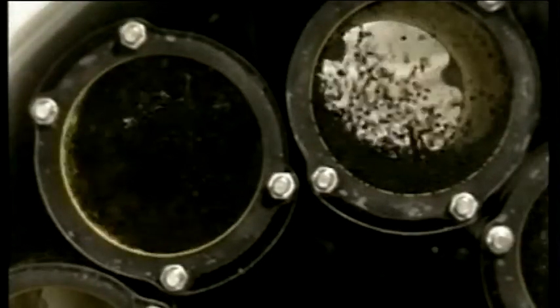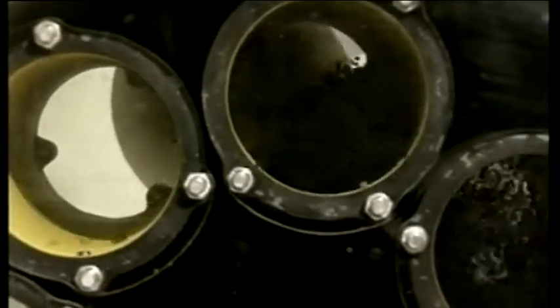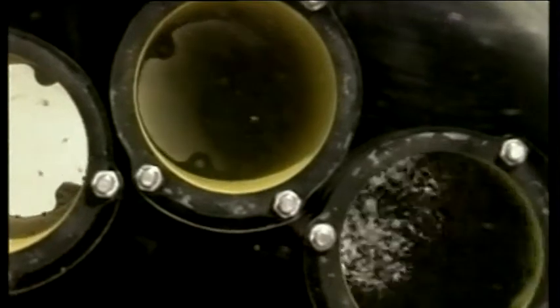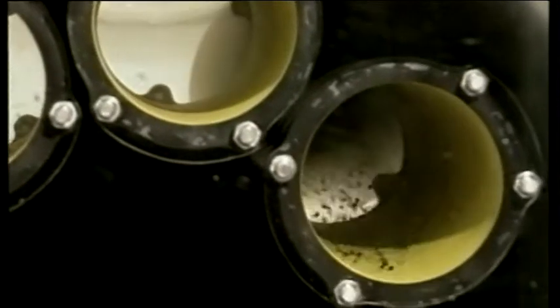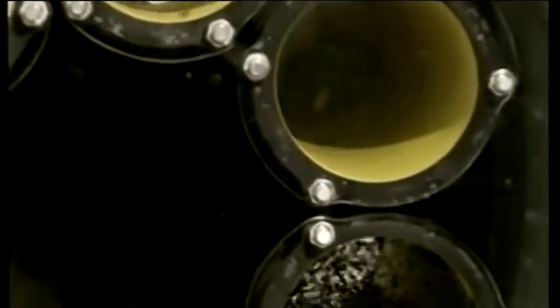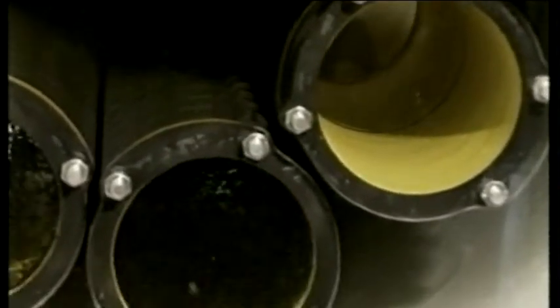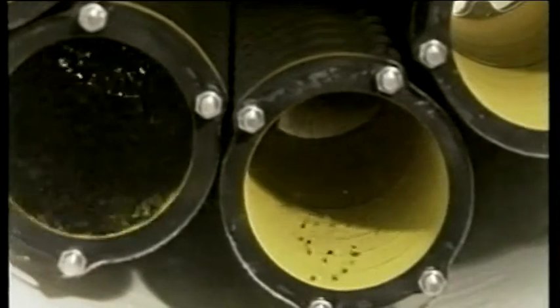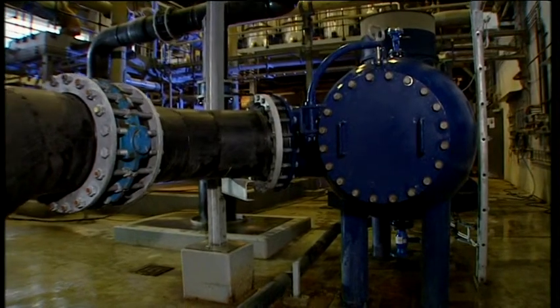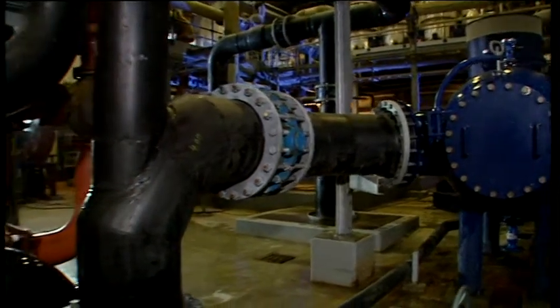The PRBW100FC fine filter, with its active filter elements, is able to filter large cooling water quantities down to 100 microns. This not only reduces the risk of blockages, but also extends the operating time of the plate-type heat exchangers between manual cleaning intervals.